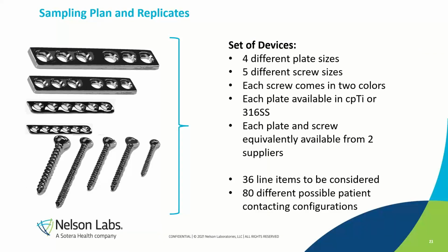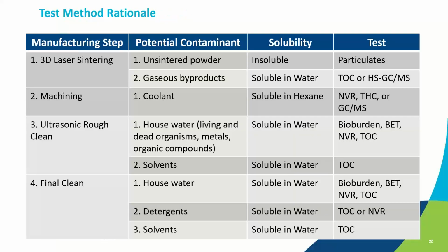You know what? There wasn't a slide for cytotoxicity. I do want to emphasize cytotoxicity. I know we talk about this a little bit later in the presentation, but I'm going to skip back here. Cytotoxicity is a test I would always include in the cleaning validation. It's per ISO 10993-5, and it does have scoring criteria for acceptance in this standard.